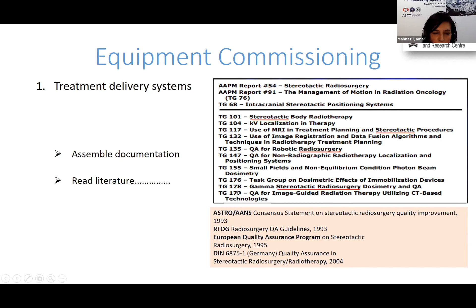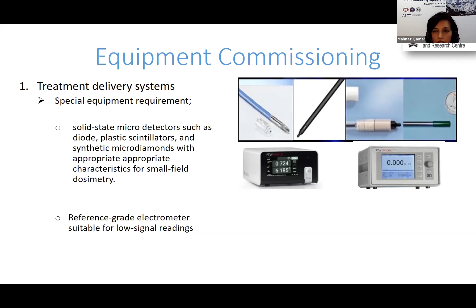I mentioned equipment. Some of the equipment we can see here are the chambers, the microchambers, and then the diodes. These days the fields are so small that some of the microchambers can introduce errors. So you really have to go to the literature, which gives you data for the different types of chambers, and there have been studies done on those. What is more common these days are the solid state microdetectors, such as diodes, plastic scintillators, and synthetic microdiamonds with appropriate characteristics for small field dosimetry. And there are reference grade electrometers which can detect low signals, so when doing patient specific QA, you're able to measure the dose properly.